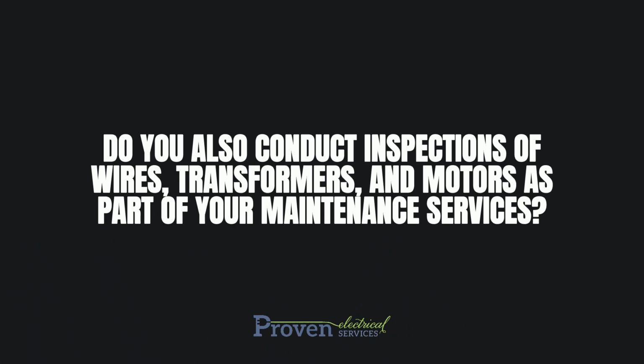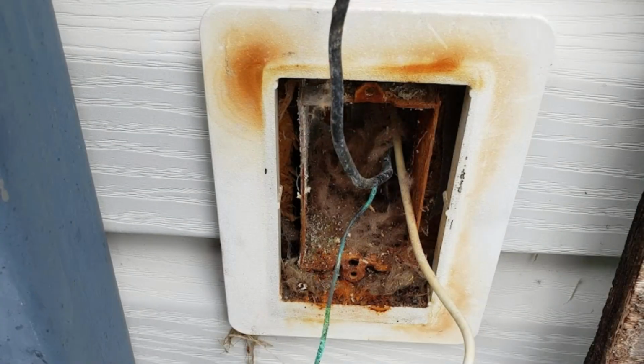Do you also conduct inspections of wires, transformers, and motors as part of your maintenance services? We will try to identify overheated or overloaded circuits, and a good way to do that is by checking the circuit breakers, motors, transformers. We can use temperature devices that read temperature, and in today's world we have thermal imaging, which enables us to check the panels, motors, that sort of thing without actually opening them up. Because sometimes in order to look at a panel close enough to identify these sorts of things without the thermal imagery, it requires opening up the equipment, which sometimes is not practical or safe to do that.